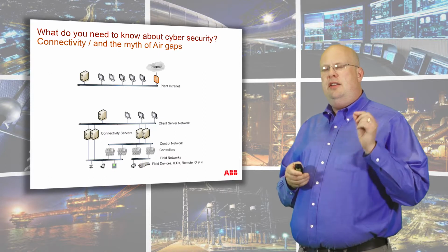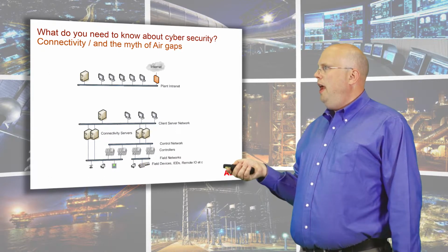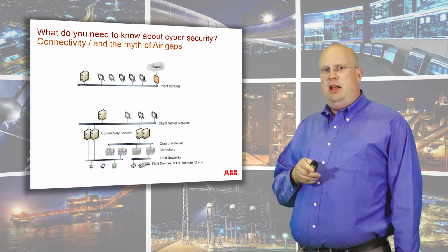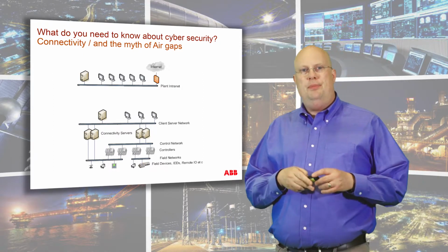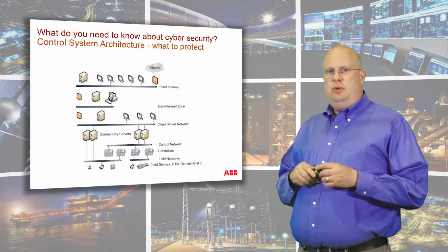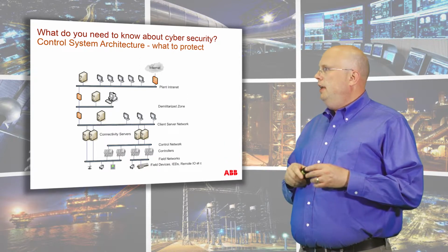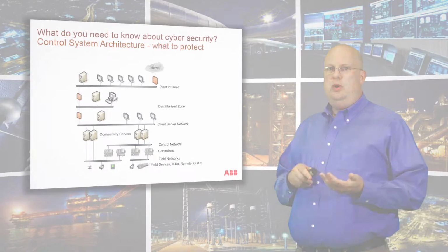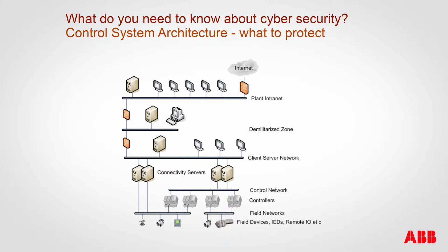It's very, very hard to do a true air gap. It can be done, but it's not worth the effort. It's very much more likely that you have a connection between, and this example is when you set it up with a philosophy called a demilitarized zone. It is the best practice approach that is reasonably secure. Basically, we have a firewall here and a firewall here, and this computer network in between is the demilitarized zone.